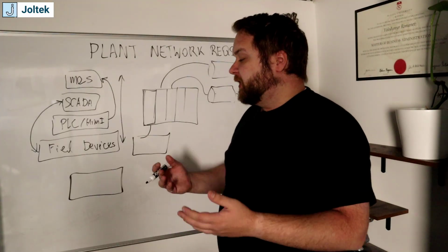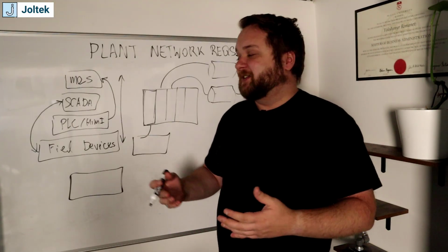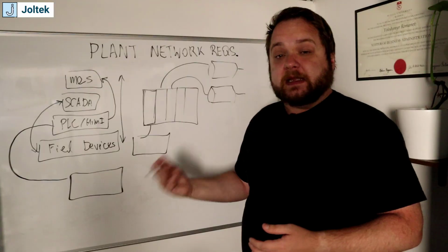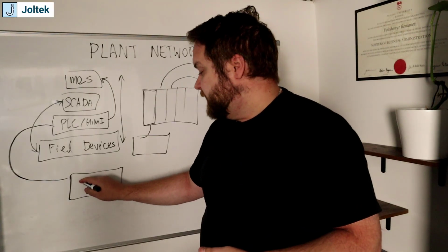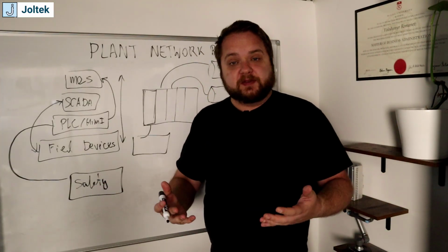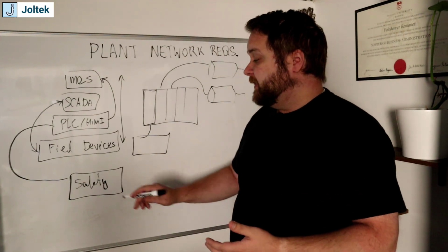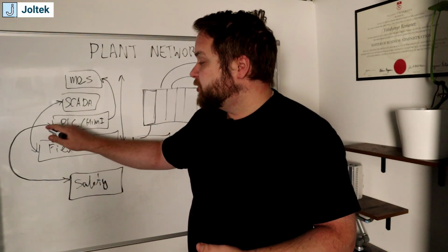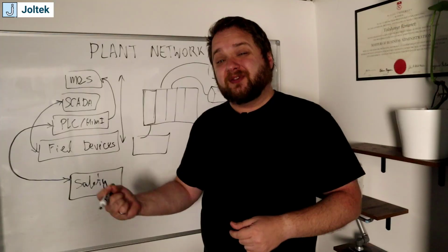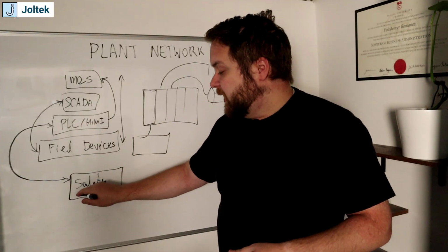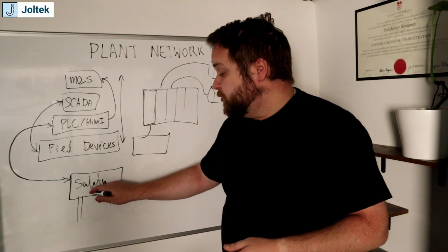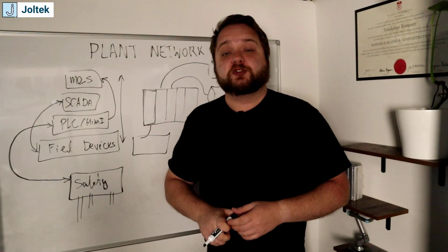I'm not going to get into the costs of wiring and why this saves a lot of time, but basically you now have safety PLCs that can communicate over an Ethernet-based network to your field safety. So I'm going to call this safety, and it has all sorts of different requirements depending on the level of safety your system needs. Basically, the network required to make sure this operates correctly needs to be very robust, very reliable, because you have different handshakes happening between the PLC and the safety device, which will then have dual channel redundancy and some other features that you would not necessarily care about in the traditional sense.